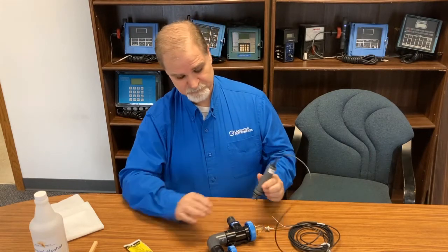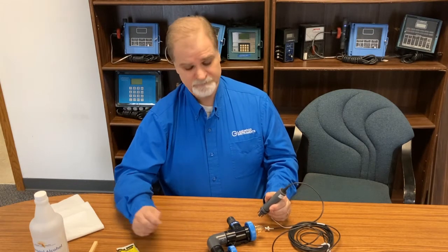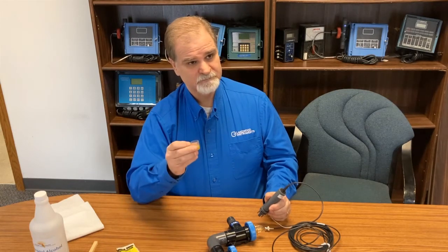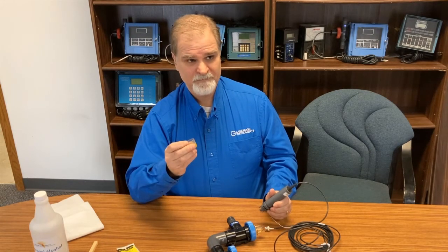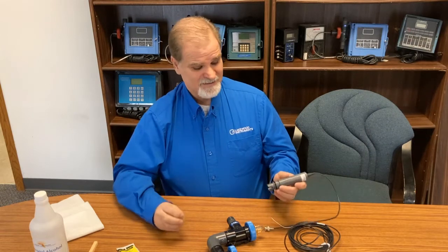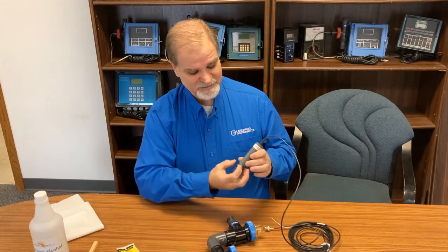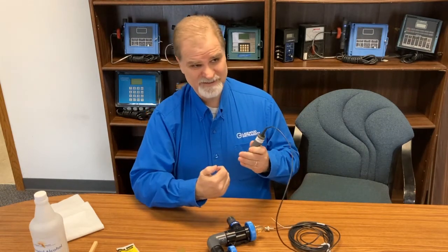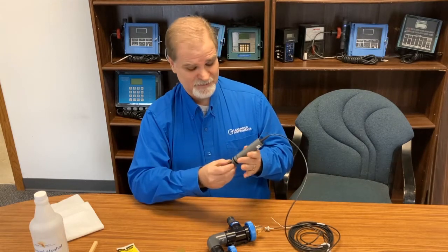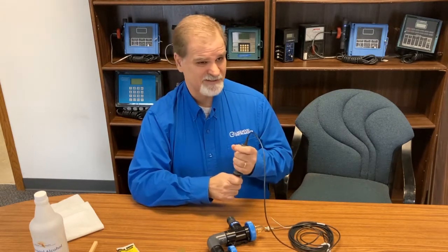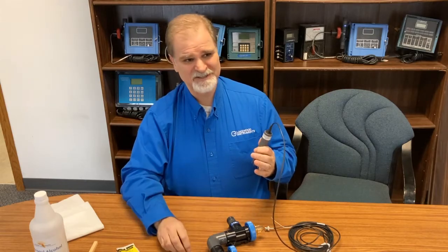Perfect. And one question we get from time to time is somebody who is in the field, they're going to pull a sensor out and they want to store it, they want to keep it, and so they have a cap and they don't have any storage solution. So should they use DI water? Oh, absolutely not. Why not? The DI will actually leach the chemicals out of the probe itself, and it will kill it. So you don't want to use DI water or distilled water. Too pure water will actually kill it quickly.